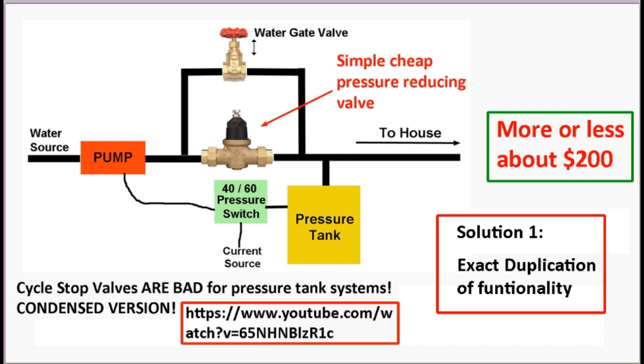Particularly they got confused by this bypass thing here, and they didn't understand that you have to set this valve so that you only get a trickle of water, what a cycle stop valve calls a dribble of water, in their patent. And so by getting a dribble of water that bypasses the pressure reducing valve, you essentially get exactly what a cycle stop valve is. A cycle stop valve is a pressure reducing valve with a leak inside.